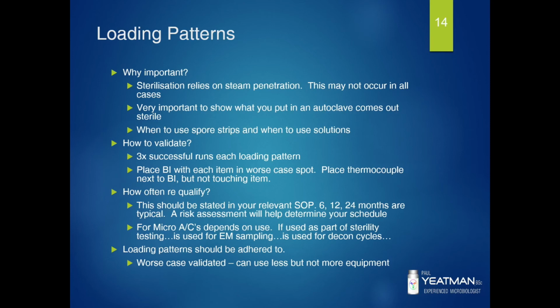When using a worst case load, you also need to consider the physical features of the load. So is the equipment liquid, solid, porous, or something else, for example? Different materials may require their own worst case determinations, so you might need to validate additional loading patterns. So that's up to you with your documentation and your risk assessments.